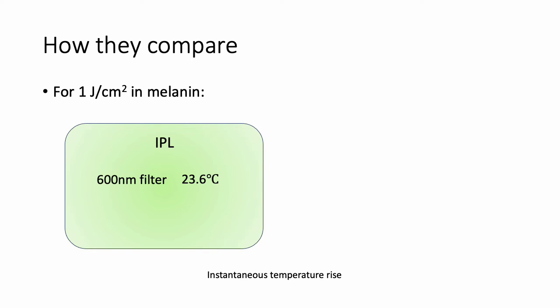How do these compare? For a 1 joule per square centimeter fluence into melanin, if we use a 600 nanometer filter on an IPL system, the instantaneous temperature rise would be about 23.6 degrees Celsius — assuming no heat losses during the pulse, so we're talking about an extremely short pulse, approximately 0 milliseconds. A 530 nanometer filter, typically used for blood vessels, will generate a temperature of around 36.7 degrees Celsius. The lower 480 nanometer filter, usually used for acne and pigmentation, will generate 52 degrees Celsius. All these use 1 joule per square centimeter — all we're changing is the filter, and as the filter value decreases, more energy gets through to the skin.